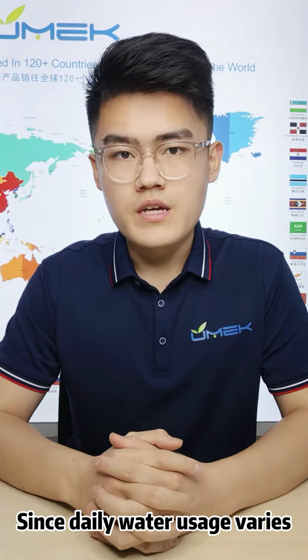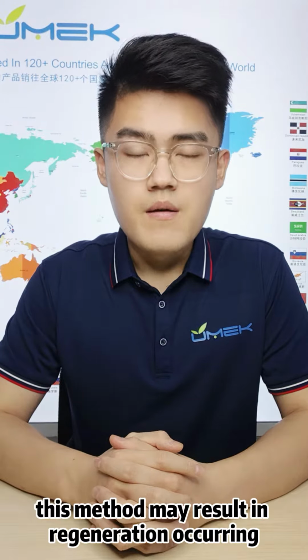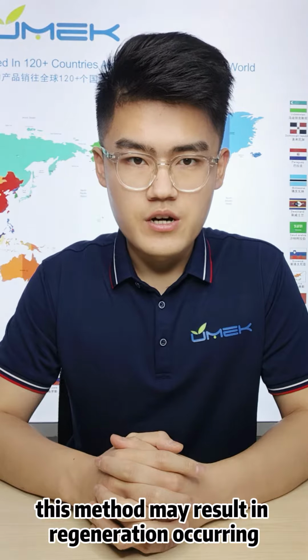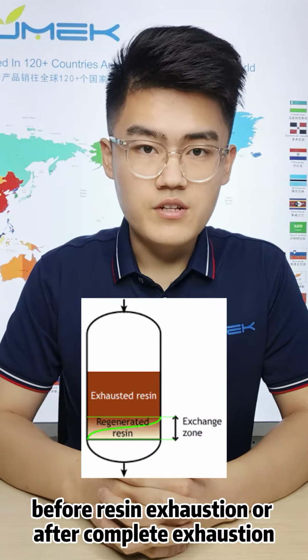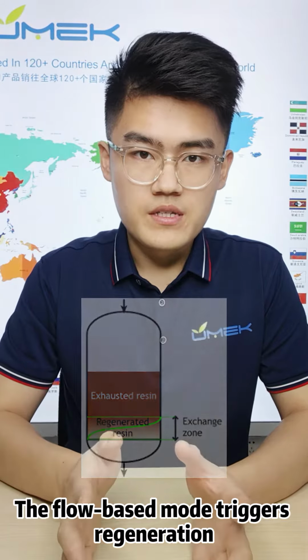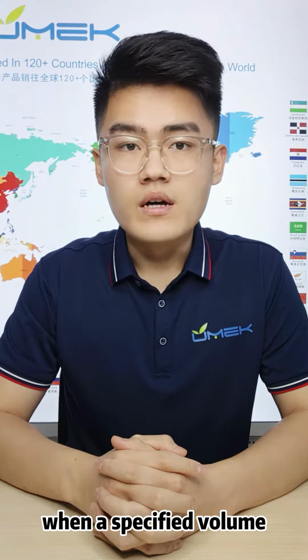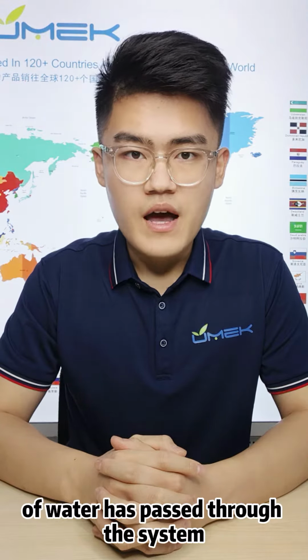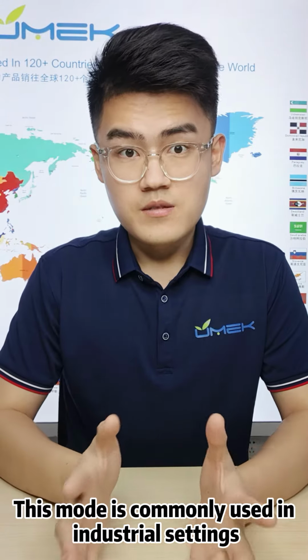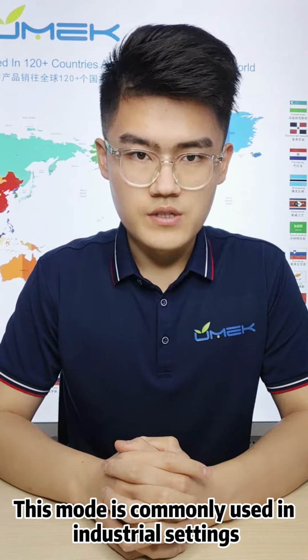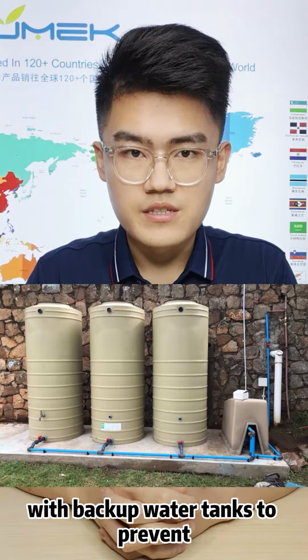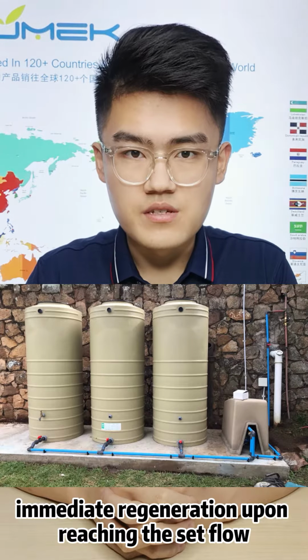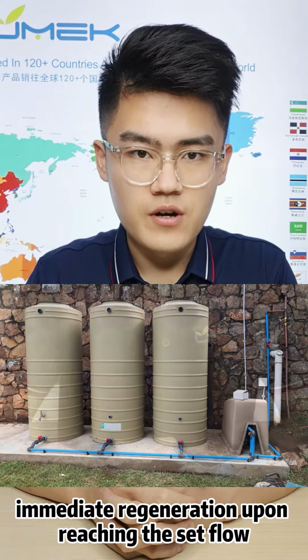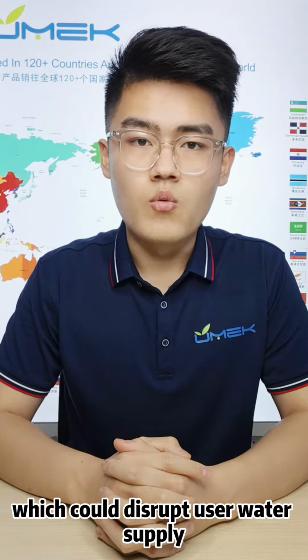Since daily water usage varies, this method may result in regeneration occurring before resin exhaustion or after complete exhaustion. The flow-based mode triggers regeneration when a specific volume of water has passed through the system. This mode is commonly used in industrial settings with backup water tanks to prevent immediate regeneration upon reaching the set flow, which could disrupt user water supply.